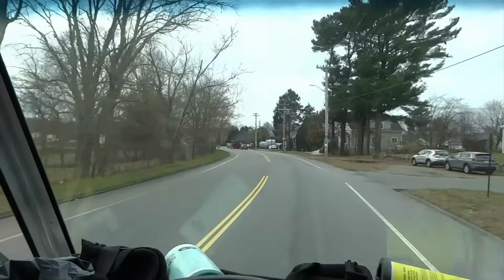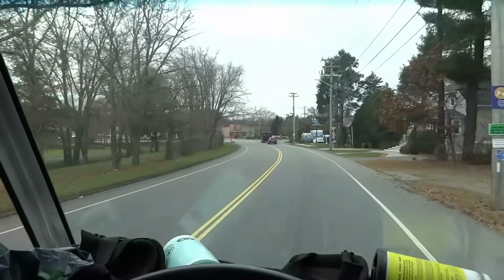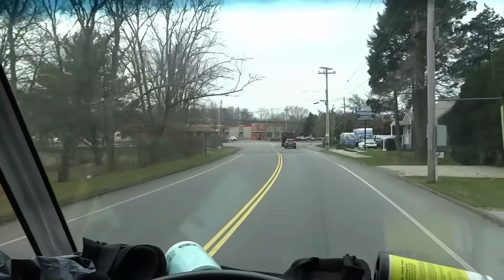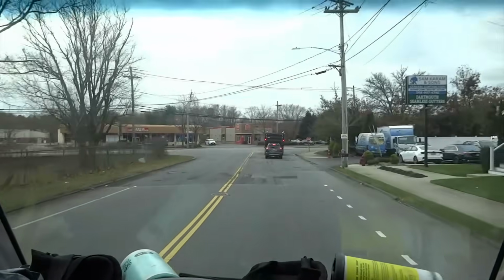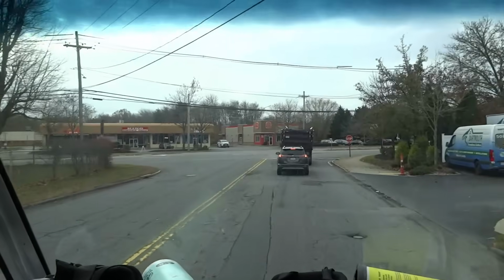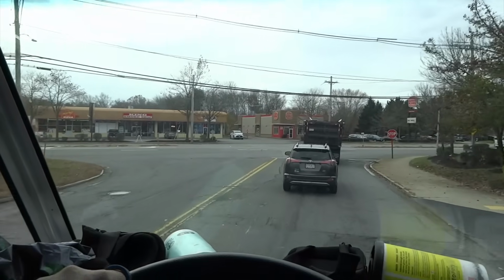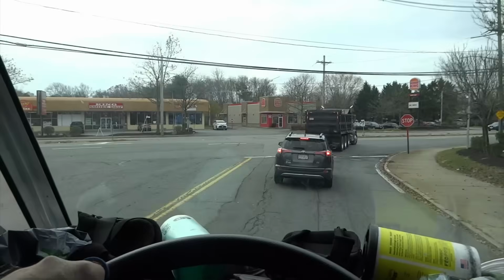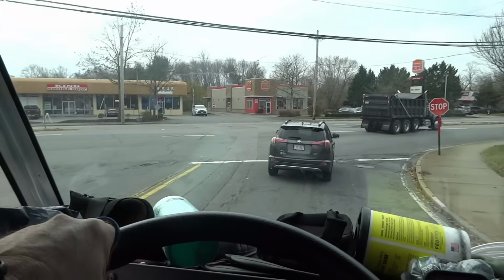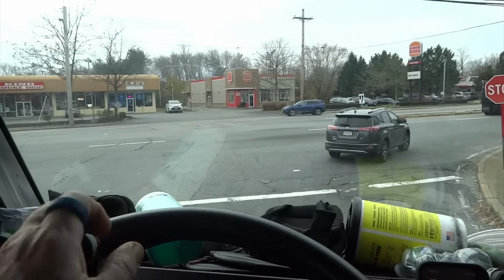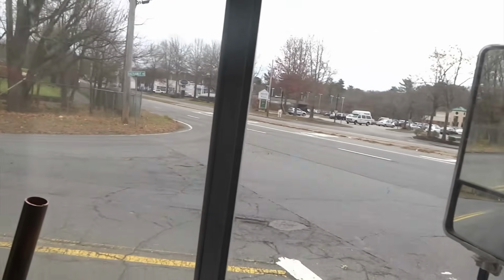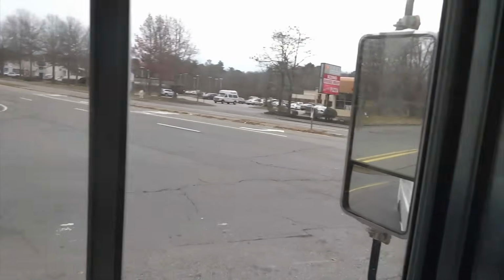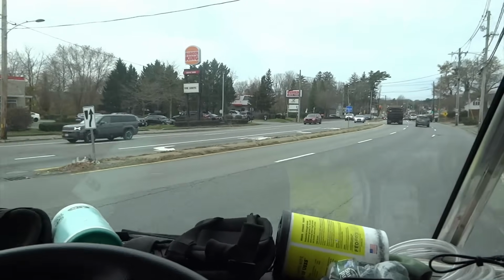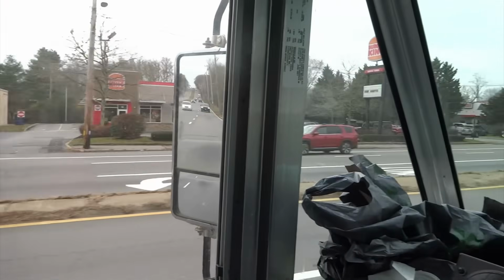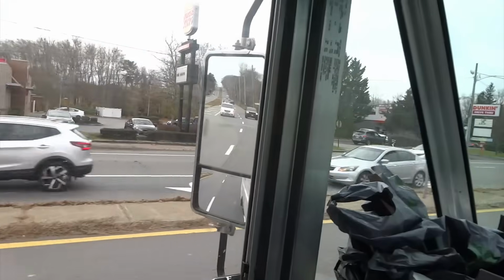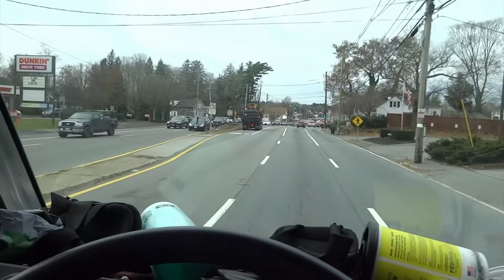But we're going to go over there and see what's ailing this thing. I was just over there recently, maybe a month ago, 2 months ago, and did a service on it. Changed the filter. The filter is by the burner. It's a two-pipe, overhead line, Roth tank outside. So it hasn't really been that cold out to be an issue with that. Unless the pump went wacky on us.